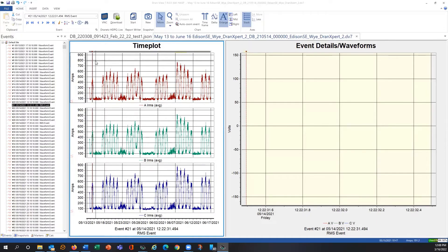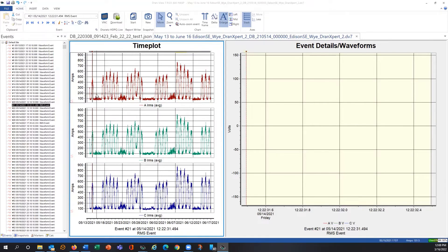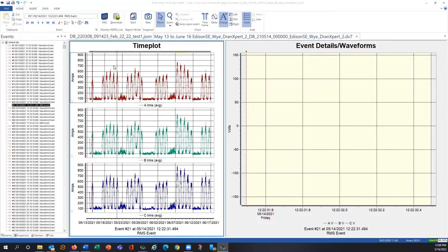You can see surveys here — this is about five and a half weeks worth of data from our service entrance. Here's a weekend, then Monday, Tuesday, Wednesday, Thursday, Friday, and then the weekend again. Not much happens here on a weekend; occasionally some folks will come in. So you'll see a demand trend that looks similar to this.